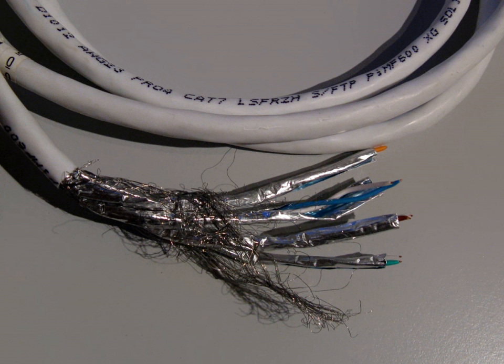Class A link channel up to 100 kHz using category 1 cable and connectors. Class B link channel up to 1 MHz using category 2 cable and connectors. Class C link channel up to 16 MHz using category 3 cable and connectors.